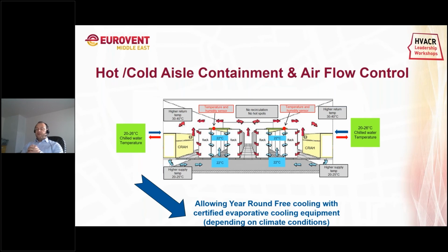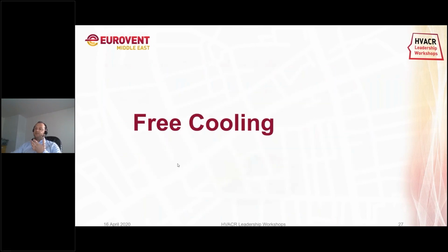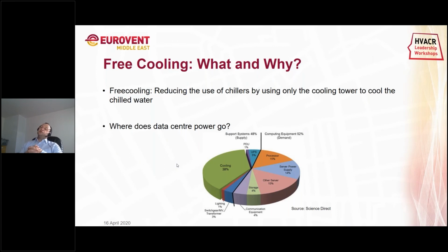Now we already touched on the topic of free cooling, and this is the last topic I want to discuss a little bit more. So, what is free cooling? Free cooling is in fact reducing the use of chillers by using only the cooling tower to cool the chilled water. And why is it important? If we see in the figure where most of the data center power is going, we see that cooling represents the biggest part of the data center power consumption. So it's very important to look into that part and to have the biggest saving there, and that can be achieved with free cooling. Also, free cooling was initially a secondary mode and mechanical operation with chillers was the primary mode, but we see more and more a shift where free cooling becomes the primary mode and chiller operation is the secondary or support mode.